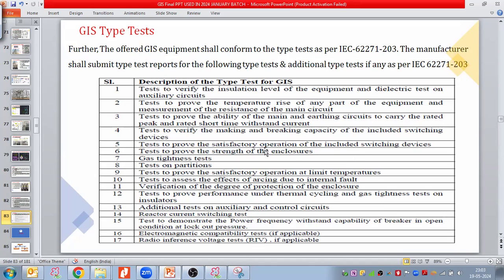Generally, these kinds of tests are done by the manufacturer: tests to verify the insulation level of equipment, dielectric tests on auxiliary circuits, tests to prove the temperature rise of any part of the equipment, measurement of the resistance of the main circuit, tests to prove the ability of main and earthing circuits to carry rated peak and rated short-time withstand current, tests to verify making and breaking capacity of the included switching devices, tests to prove the satisfactory operation of the included switching devices, tests to prove the strength of the enclosure, gas tightness test, tests on partitions, tests to prove satisfactory operation at limit temperatures, tests to assess the effect of arcing due to internal fault, verification of the degree of protection IP class of the enclosure, tests to prove performance under thermal cycling and gas tightness tests on insulators, additional tests on auxiliary and control circuits, and reactor current switching test if we are using a reactor in the substation.